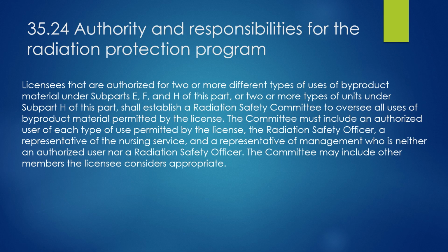So licensees that are authorized for 2 or more different types of byproduct material must have a radiation safety committee. And the Radiation Safety Committee's job is to oversee all uses of byproduct material. The committee must include an authorized user, the RSO, a representative of nursing, a representative of management, and the committee may include other members the licensee considers appropriate. Best practice would have a representative from each of the modalities. You'll see that most hospitals have to have a radiation safety committee, and so that will be made up of an authorized user who is typically a radiologist, but it's a physician that's listed on the license, the RSO, a representative of nursing, a representative of management, and then usually a representative from at least one or more or all of the modalities.